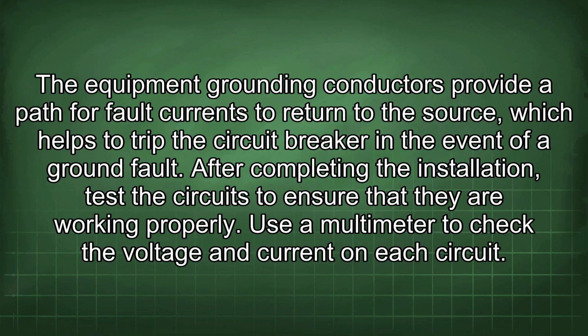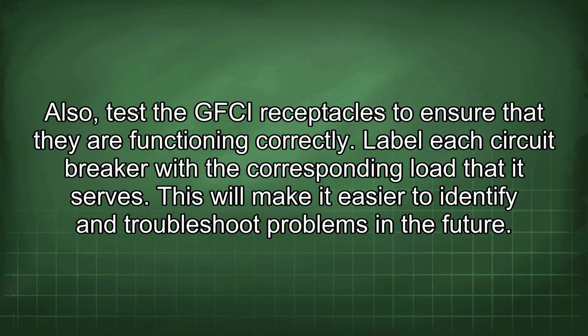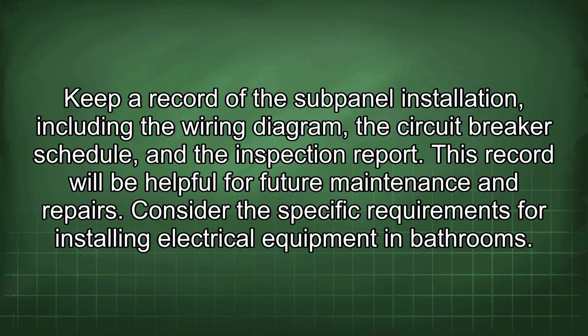After completing the installation, test the circuits to ensure that they are working properly. Use a multimeter to check the voltage and current on each circuit. Also, test the GFCI receptacles to ensure that they are functioning correctly. Label each circuit breaker with the corresponding load that it serves. This will make it easier to identify and troubleshoot problems in the future. Keep a record of the subpanel installation, including the wiring diagram, the circuit breaker schedule, and the inspection report. This record will be helpful for future maintenance and repairs.